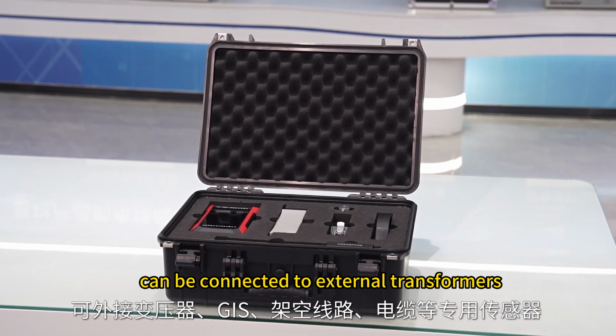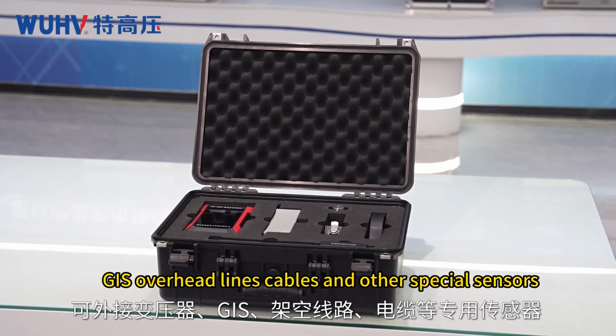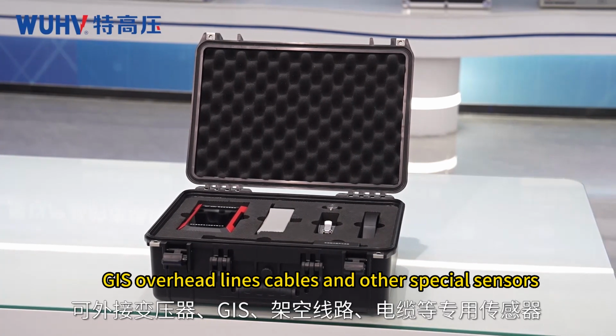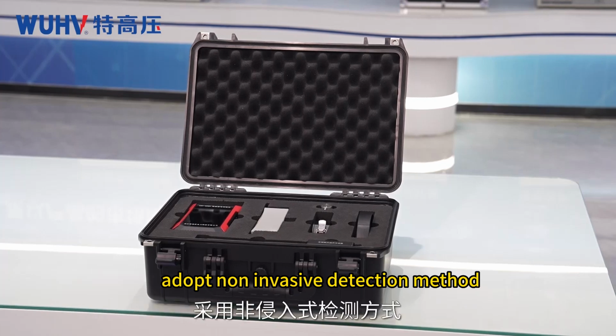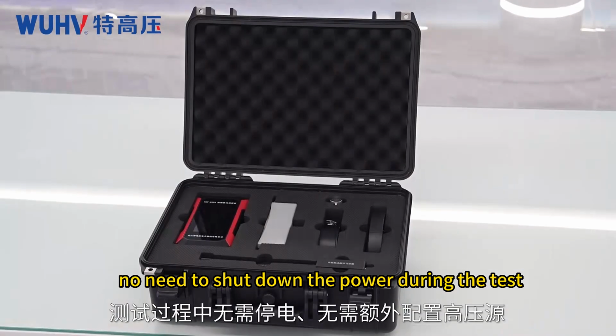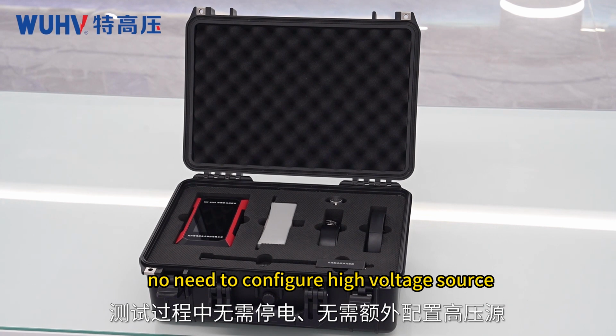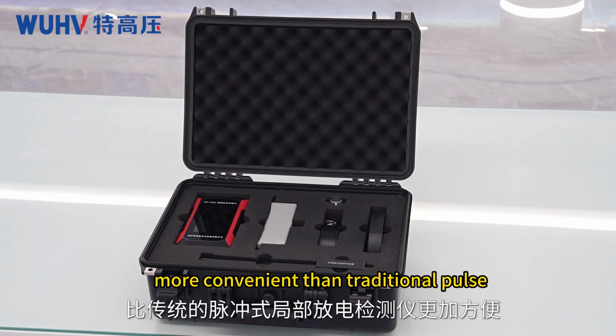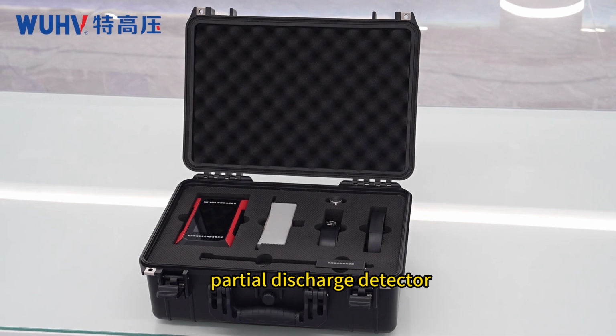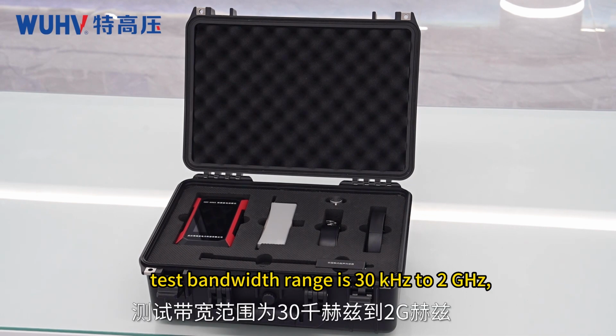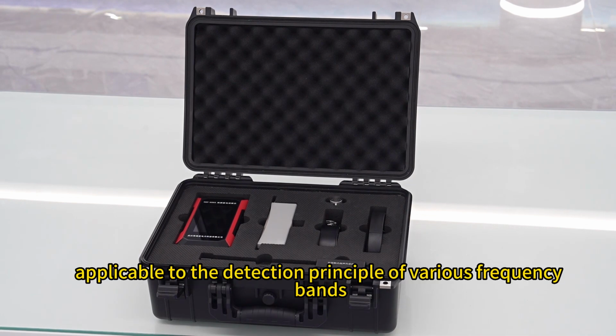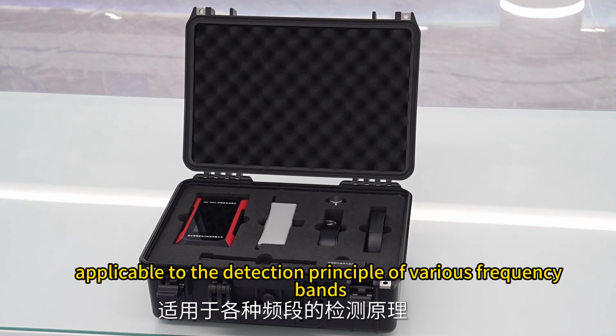can be connected to external transformers, GIS, overhead lines, cables and other special sensors, adopt non-invasive detection method, no need to shut down the power during the test, no need to configure high-voltage source, more convenient than traditional pulse partial discharge detector. Test bandwidth range is 30 kHz to 2 GHz, applicable to the detection principle of various frequency bands.